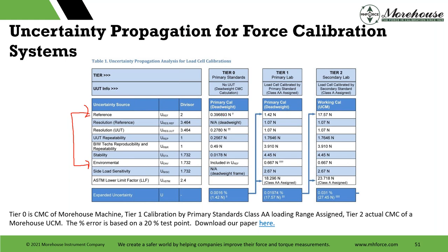Hey, we calibrate the load cell and dead weight that goes into a cal machine. So we start out in our dead weight performing calibration, hopefully on your load cell at 0.0016. You put it in the cal machine. This is the 20% force point, and this is without automation. Automation is going to lower this a bit, but this was without automation. With automation, this number is going to come down.